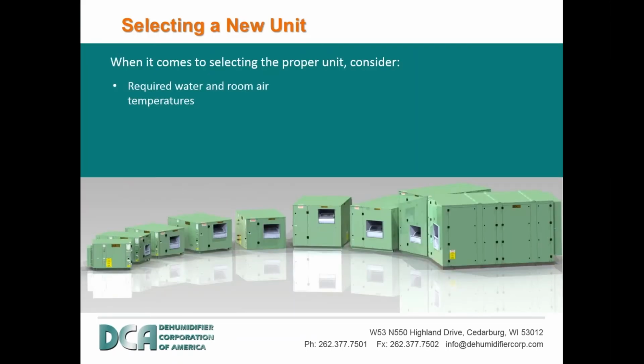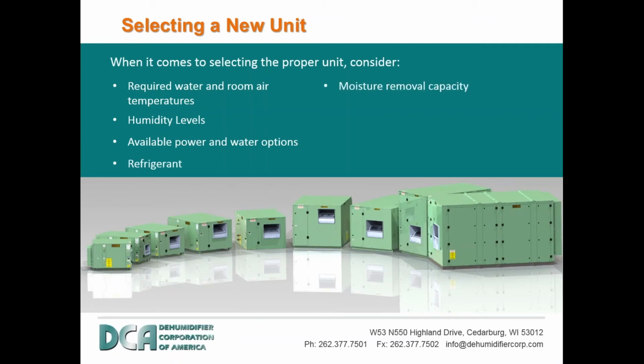Like I said before, we want to run the room air temperature 2 to 4 degrees above water temperature. Humidity levels, somewhere between 50 and 60%, probably 55 to 60% being very common. Available power and water options, as well as refrigerants, moisture removal capacity, outdoor air code requirements, cooling needs, unit weights, and others. Also, equally as important is the location of the system in terms of suitable ductwork and system serviceability.